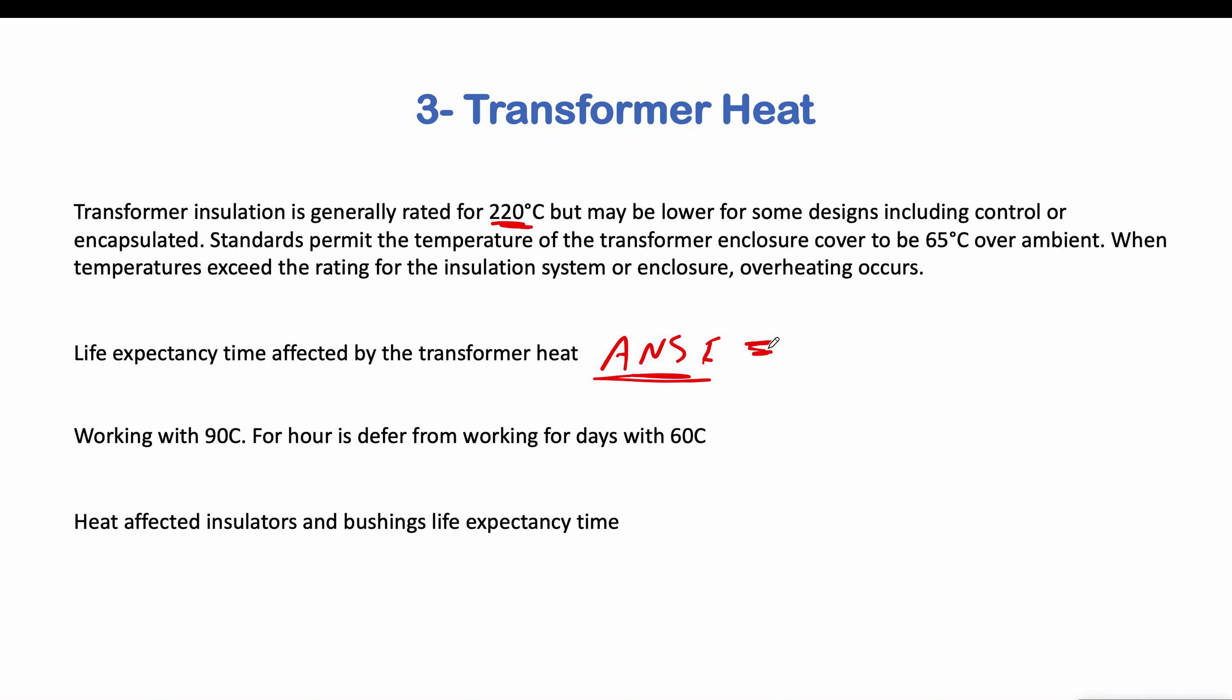plus 65, which means if the ambient temperature in the environment is equal to 30, it means that the rated temperature for this transformer is equal to 95 degrees Celsius.